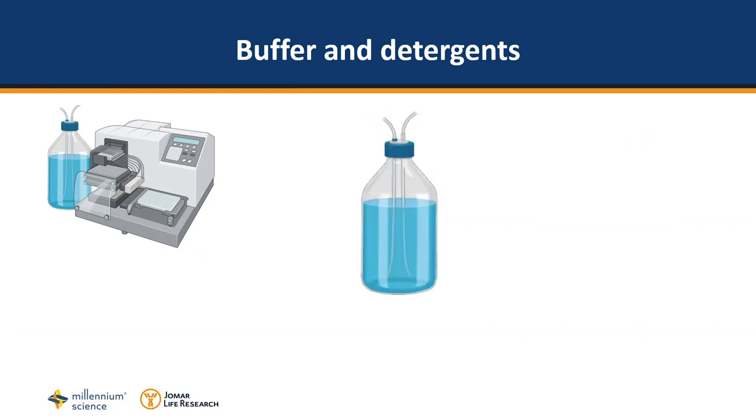The concentration of detergents is also important and should be optimized for your experiments. Too much detergent can create an excess of bubbles, which may cause an overflow of your waste buffer. Thankfully, biotech plate washers can have a liquid level sensor fitted into the waste containers.